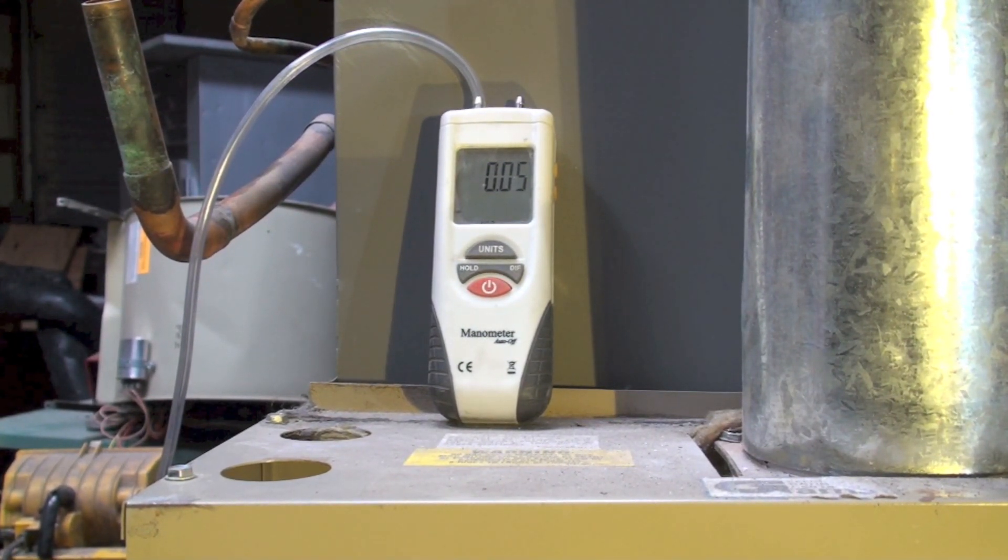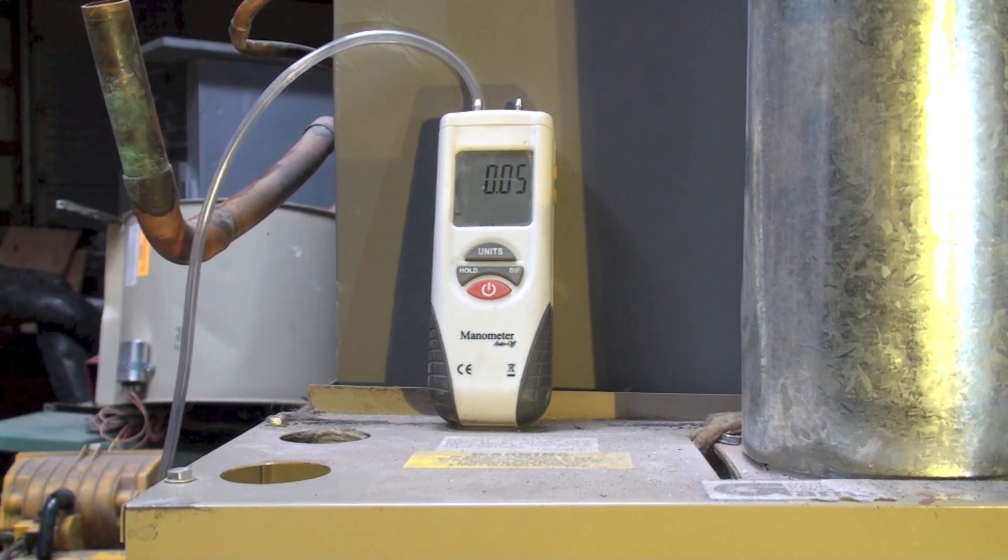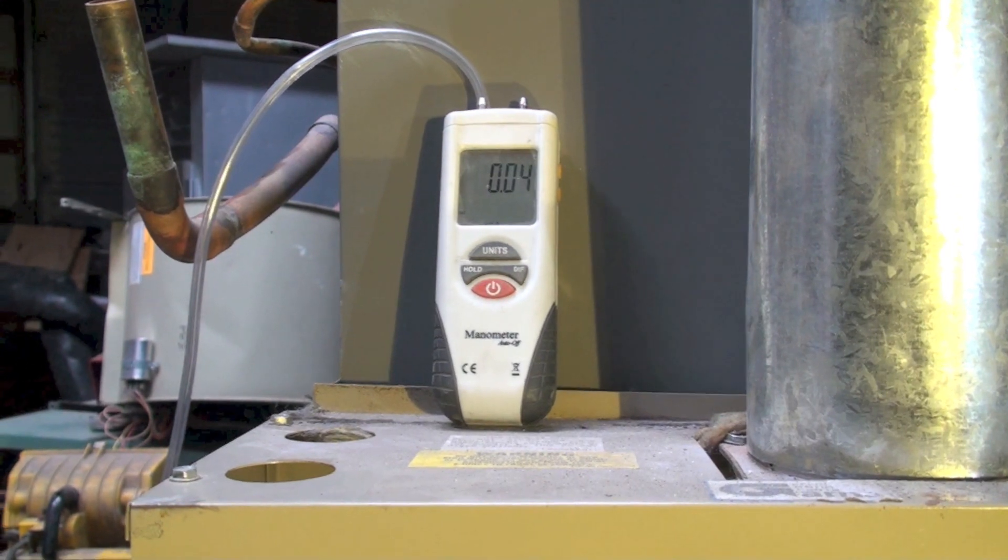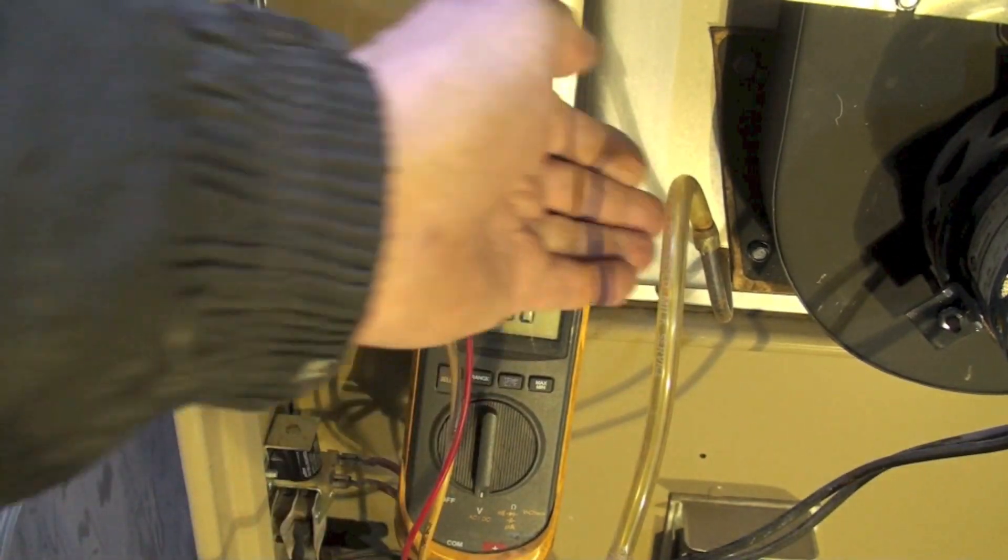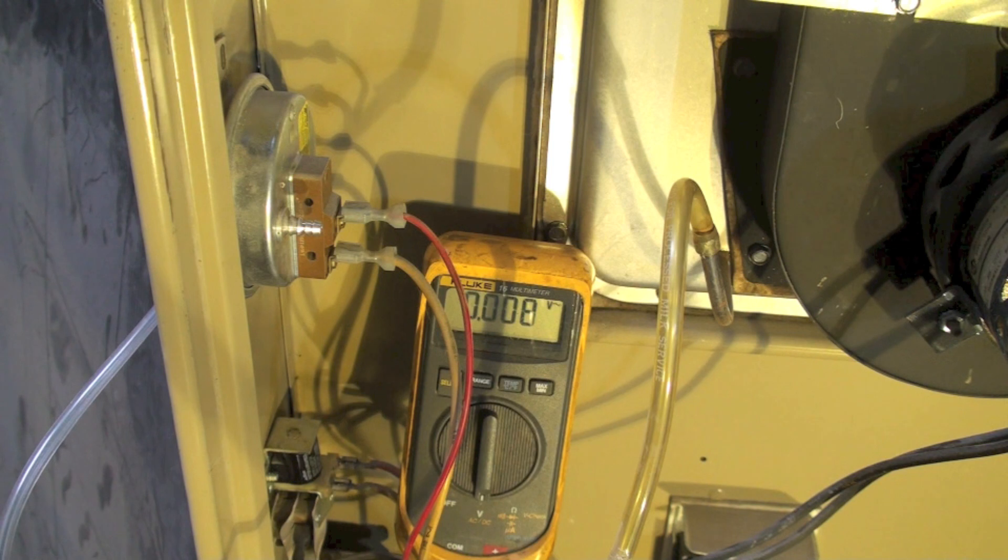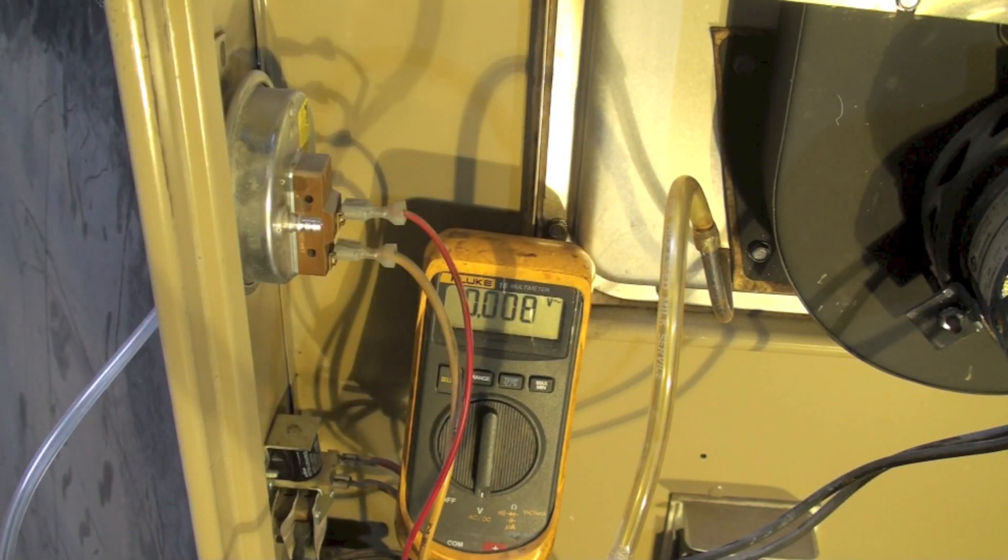Does that mean the pressure switch is bad? No, it means I got a blockage. Obviously the inducer is running. Could have a vent blockage, I could have a blockage here in the sensing tube, something like that. So I have a problem other than the pressure switch that's causing this. First I'd probably clear this tube out, maybe pull the inducer off and take a look at it and see what condition it's in. Remove the vent, see if it works with the vent removed, that sort of stuff.